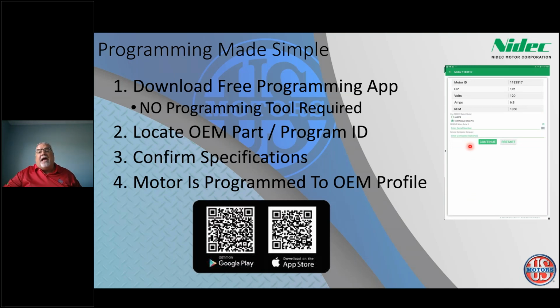So if I had that part number on the first screen, typed it in and hit enter, and it came back with, okay, the motor should be a 1/2 horsepower, 120 volt, 6.8 amp, 1050 RPM, we need to match that with the information on our original nameplate. If that matches, we're good to go. If it doesn't, then maybe one of those numbers is off, so just double check yourself. Then we tell it, yes, it's a Rescue Select Pro.